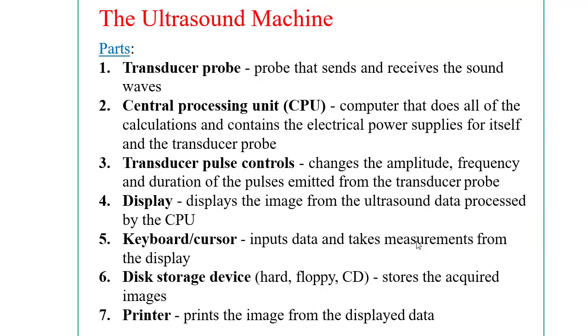The basic parts of an ultrasonography machine are: the transducer probe, which sends and receives sound waves; the central processing unit (CPU), which performs all calculations and contains the electrical power supply for itself and the transducer probe; and the transducer pulse control, which changes the amplitude, frequency, and duration of pulses emitted from the transducer probe.